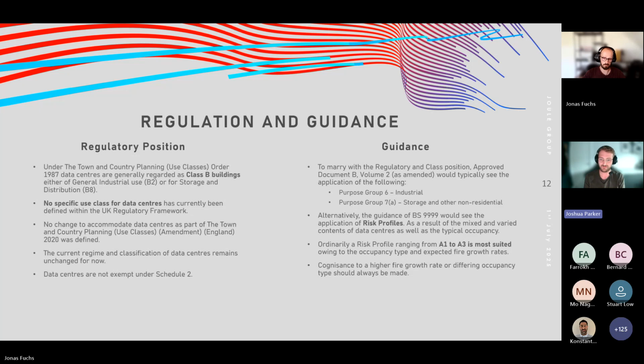It would be fair to assess that these buildings don't fall under a common building type. So we often find the most appropriate and best fitting solution is to move down a BS 9999 route through the adoption of the risk profiles, as this allows a more tailored and specific set of outcomes and variables to tailor the fire safety design to a more suitable position. Often we find risk profiles range from A1 to 3, but that can depend on various other systems within the building, be that automatic detection or suppression systems, which all have a bearing on what risk profile we apply. But more often than not, the application of BS 9999 does provide the most flexible route to fire safety compliance.